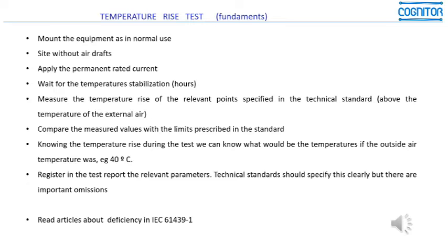We measure the temperature rise of the relevant points, as specified by the technical standards. We compare with the limits prescribed in the standard, and know the temperature rise during the test. We can know what the temperatures would be if the outside air was, for example, 40 degrees, which is the limit working temperature for the IEC standard. We register the relevant parameters in the test report, and that is it.